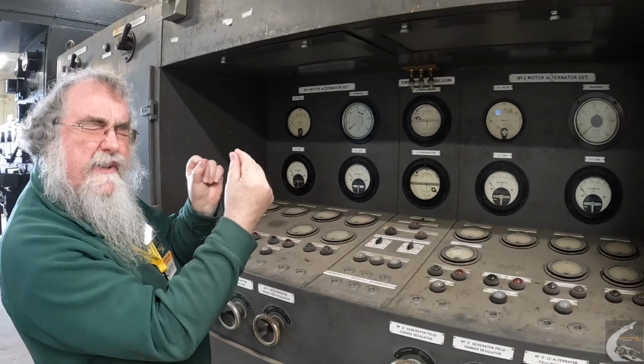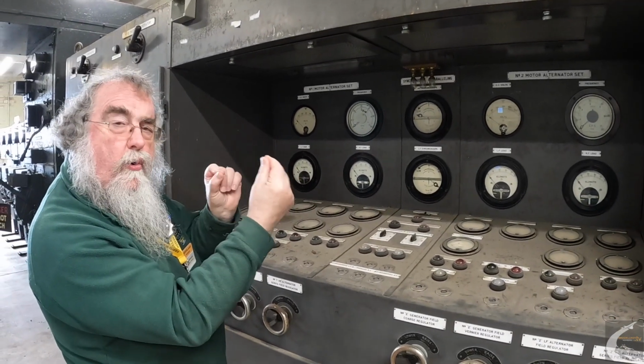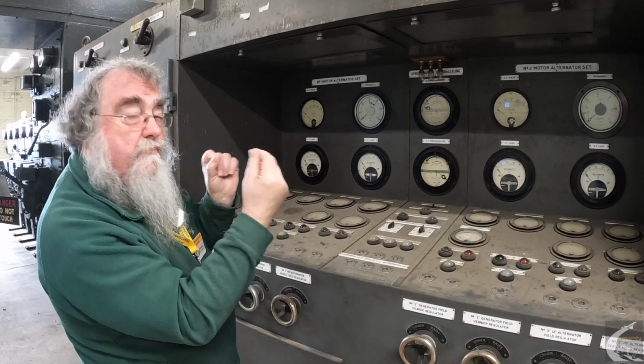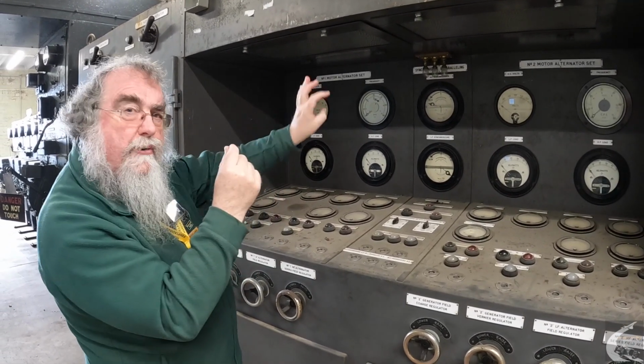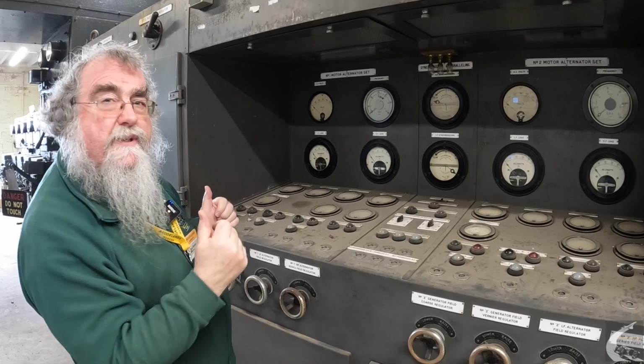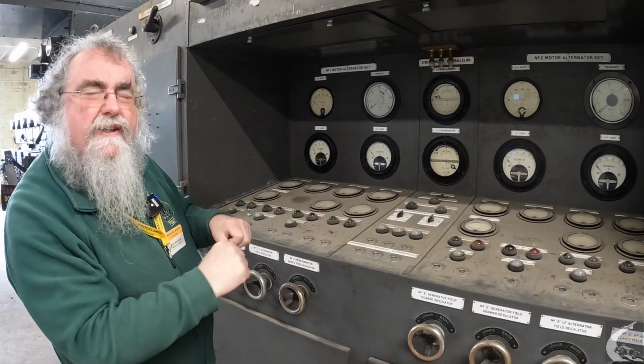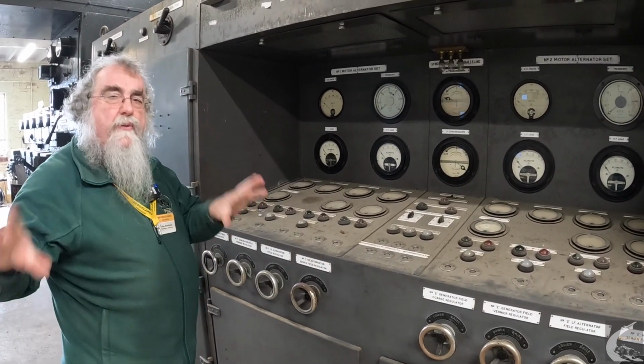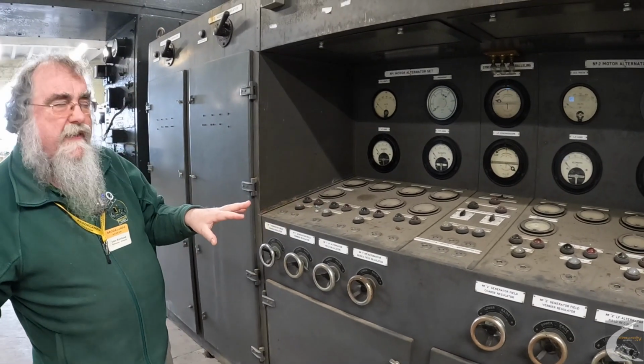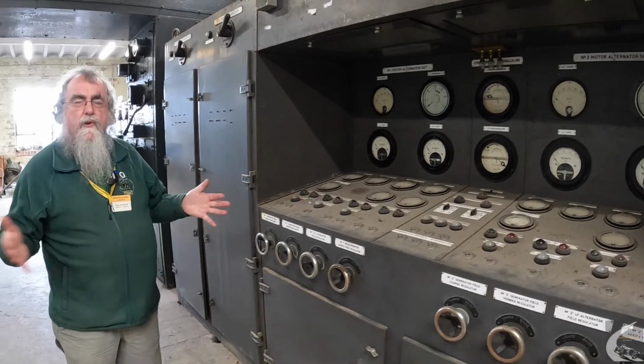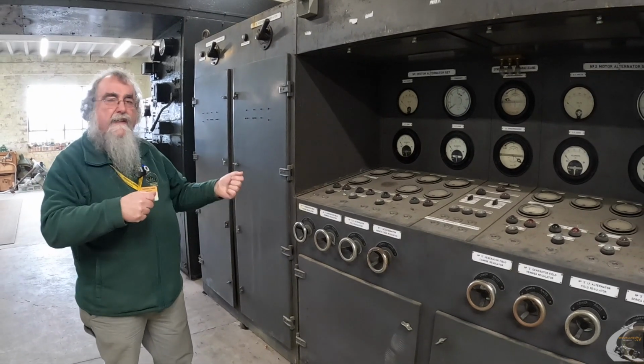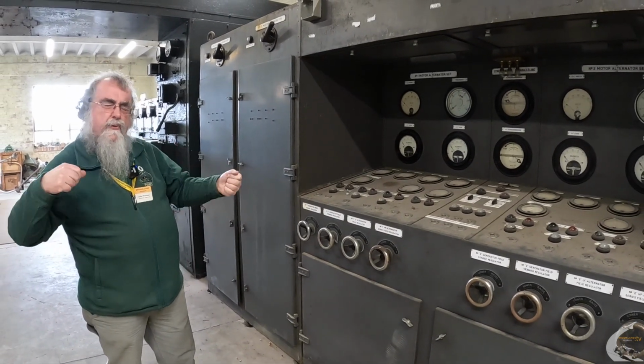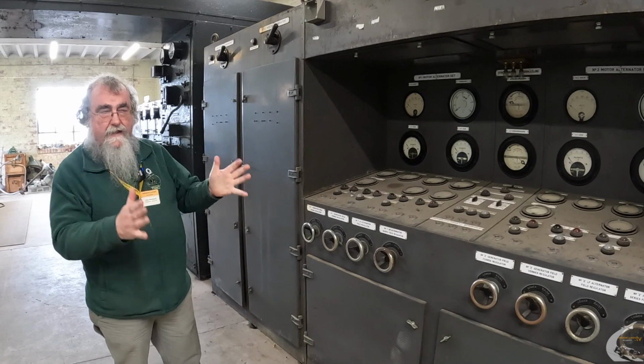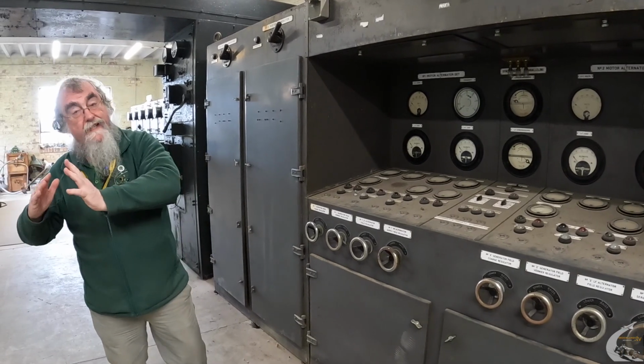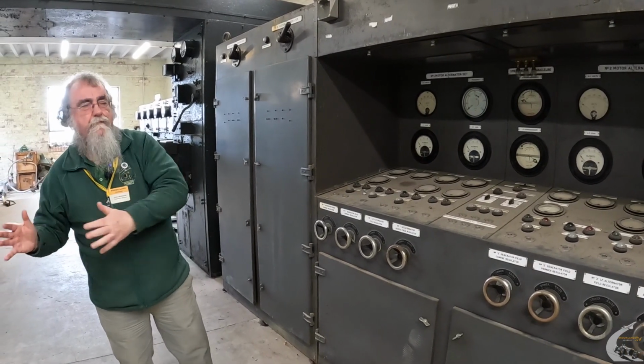So when it gets to the point where the bulbs are apparently all off, or potentially 2 of them, maybe all 3 - I'm not quite clear how it was wired - you are then in a position where you can actually synchronize and connect together both of the synchronized pieces of kit. Then they'll run off each other, so one will drive the other should more power be applied to one of the Ward Leonard sets or the other.